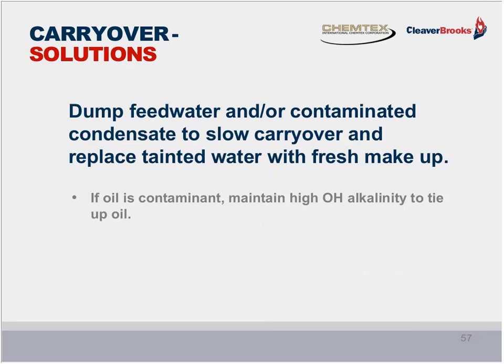The solution is to dump the feed water and or the condensate to slow the carryover and replace that tainted water with fresh makeup. If oil is determined to be the cause of carryover, additional OH alkalinity is going to have to be added to the boiler to tie up that oil and saponify it and get it down to the bottom of the boiler where it can come out. And as much as I'd like to have a better solution, dumping and flushing the system is the main way to stop the carryover. Some antifoam can be added to the system, but basically the solution is to dump the system.